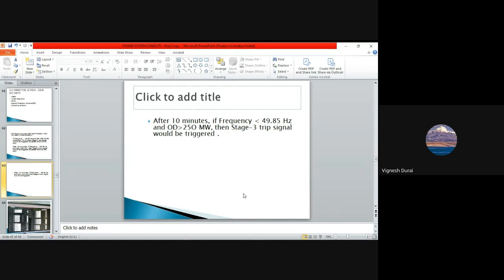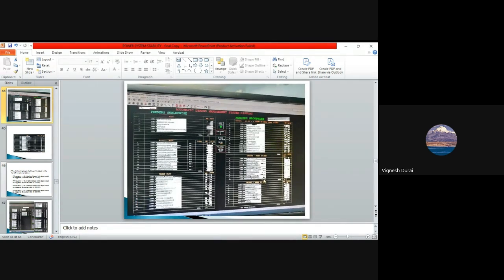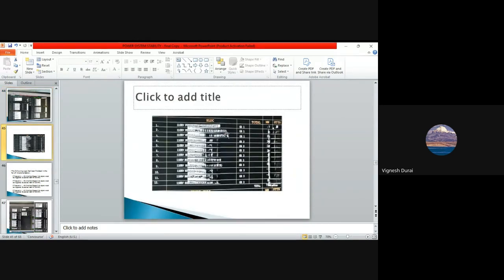For example, this is how our SCADA system will look, where we have this automatic demand management system display. In Tamil Nadu we have 3 load dispatch centers: one in Erode, next in Chennai, and one in Madurai. These are the feeders. You can see here in the Madurai load dispatch center we have group 1 tripping, where the frequency is below 49.85 and your overdrawal is more than 250 megawatt for 10 minutes, they will initiate the first tripping. If the condition still prevails, it will go for group 2 tripping. Again, if it prevails, it will go for group 3, so that you will get a relief of 600 megawatt.